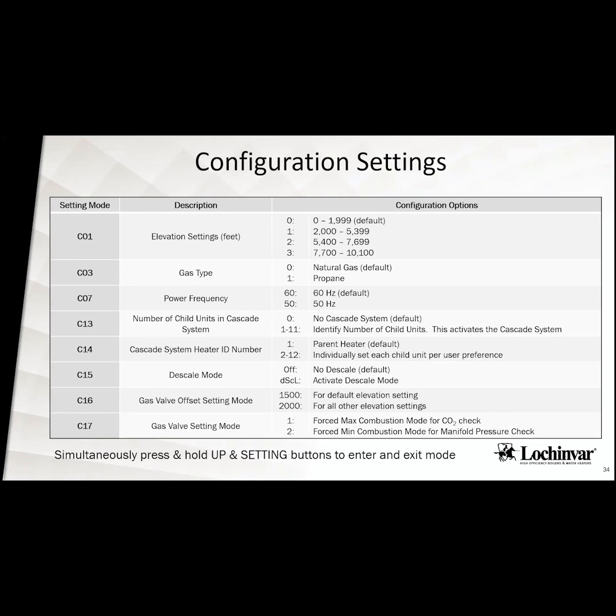This is where you'd also go if you wanted to change that unit to activate descale mode. That descale mode is going to come up. It's going to let you flow solution through that unit for a certain amount of time. So it's going to let it go through the heat exchanger. It's going to let it go through the bypass.